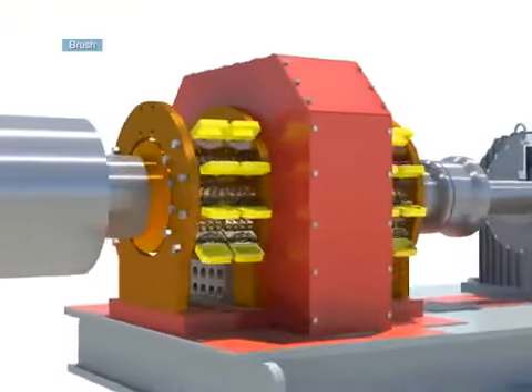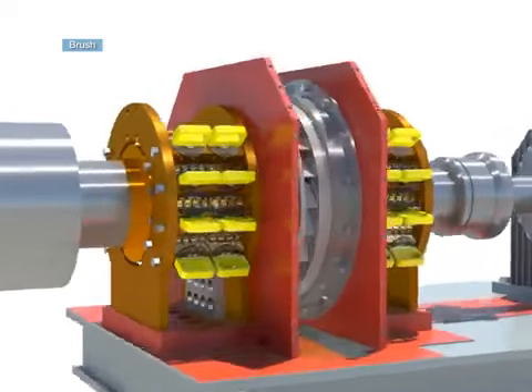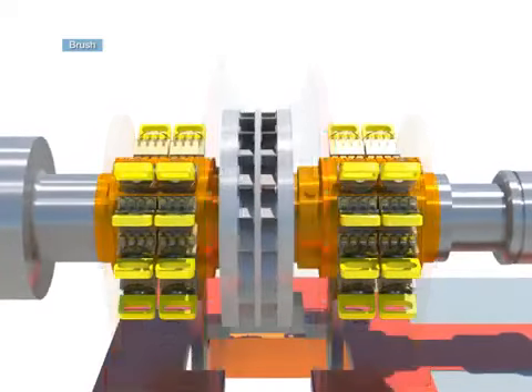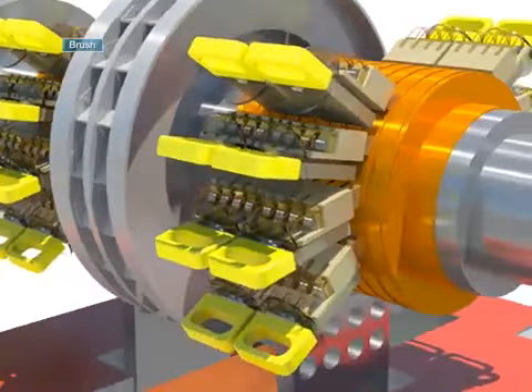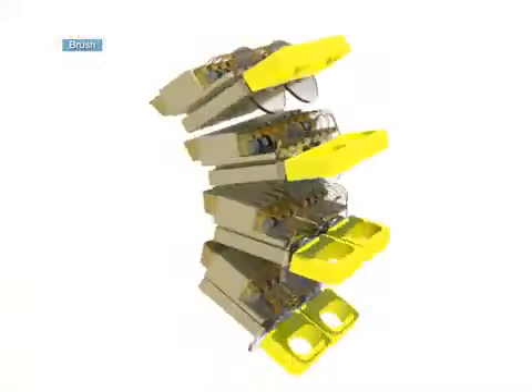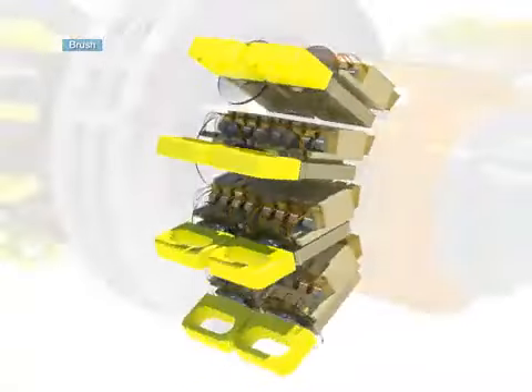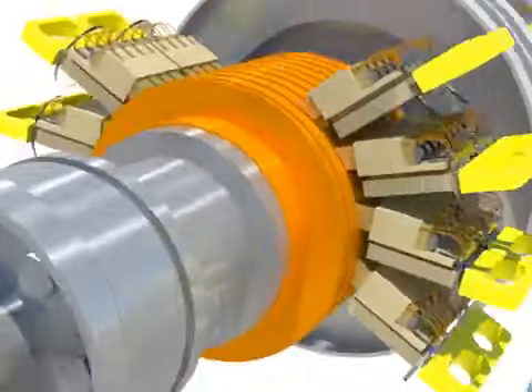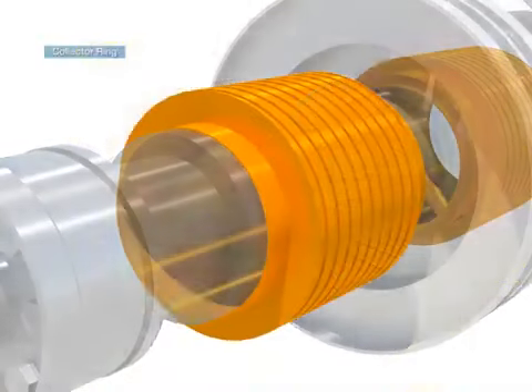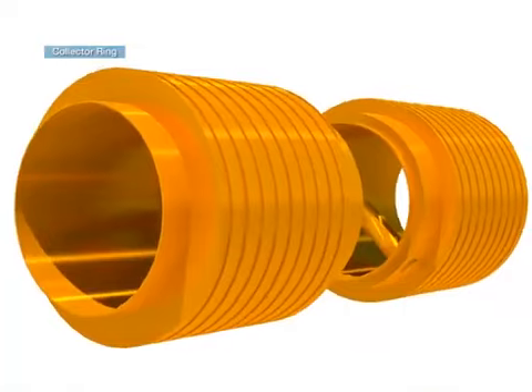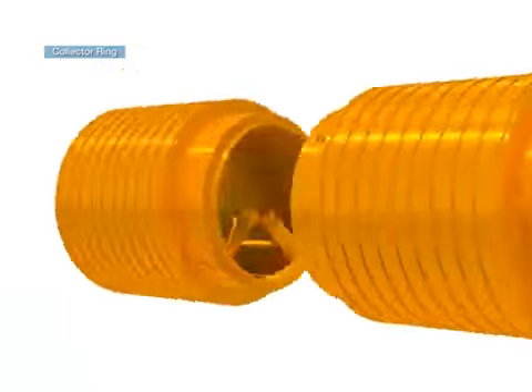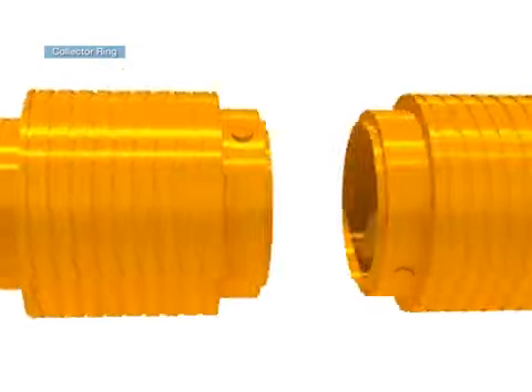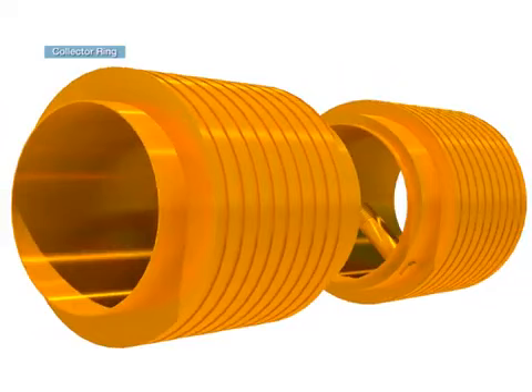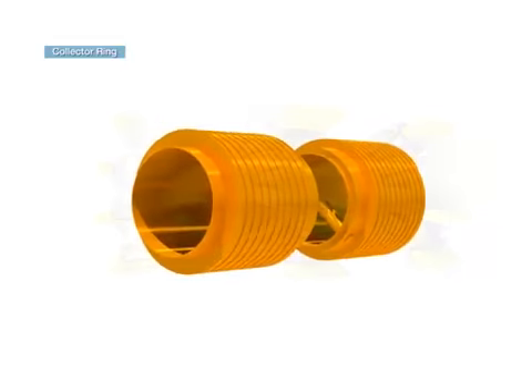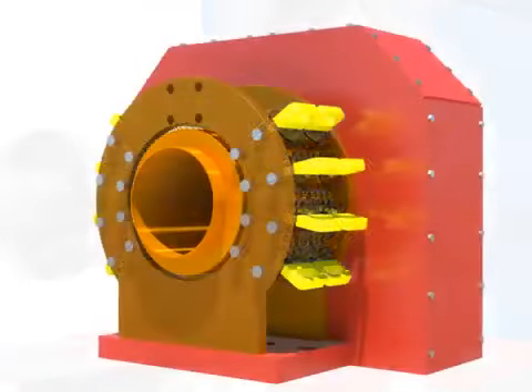The brush is a part which is installed on the surface of the collector ring to make sliding contact to apply an electric current between the electric circuit of the generator rotor and the external circuit. The collector ring is a cylindrical ring installed on the surface of the rotor shaft to provide direct current produced in the exciter to the rotor winding. Direct current is provided through the brush.